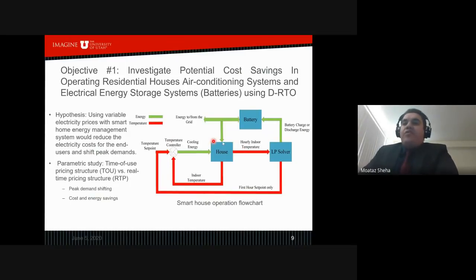So we have our house here, with some indoor temperature. Let's go this direction first: the indoor temperature goes to a linear programming solver, which gives you the temperature set point for the next hour. You take this to a temperature controller, basically a PI controller, and using the indoor temperature and the new set point, it determines the amount of cooling energy needed to reach the set point.